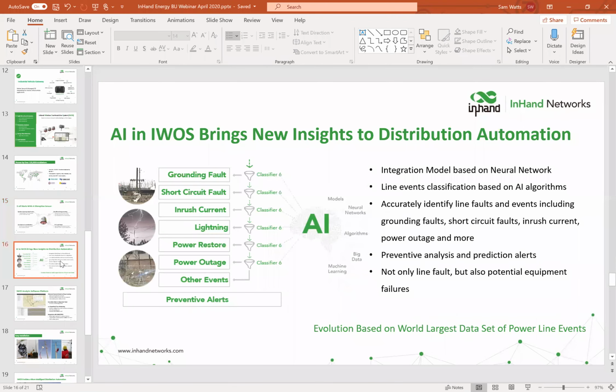So we have this very interesting fault algorithm that we developed 4 years ago, as I mentioned. This is actually running in the concentrator in the field, on the edge, continuously going over the incoming sensor data that's being sent in 256 times a second.